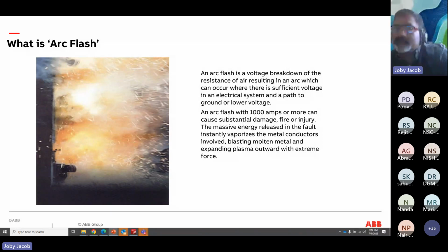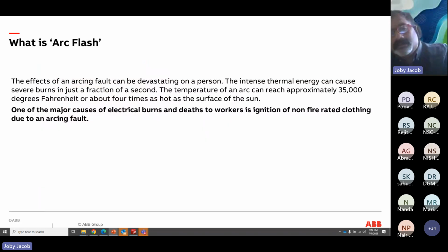An arc flash of 1,000 amps or more can cause substantial damage like fire and injury, and massive energy is released in the fault. Basically, it instantaneously vaporizes the metallic conductor. Normally, copper expands 65,000 times, and it splashes like molten metal around the surroundings. The metal and expanding plasma exert extreme force. So the effects of an arc flash can be devastating if you are standing in front of it.